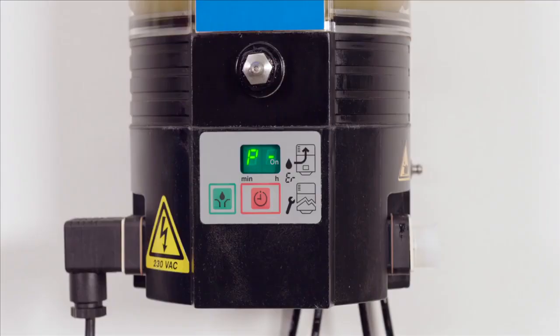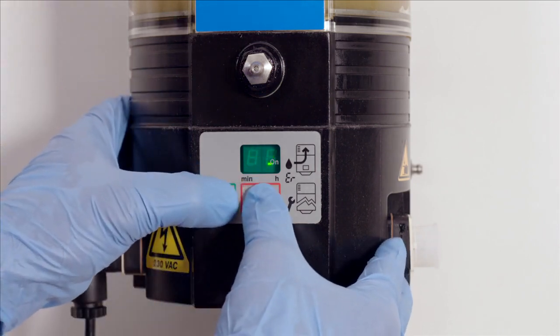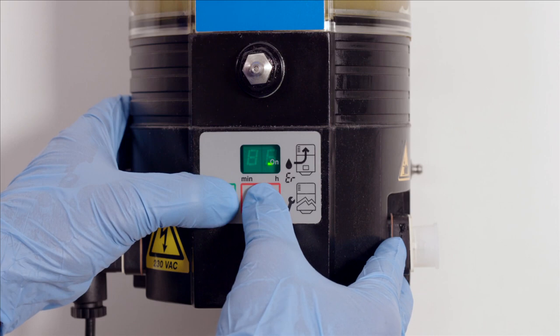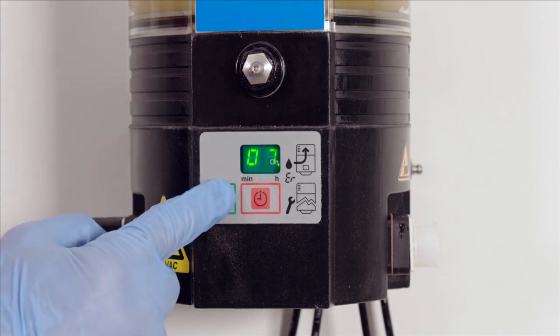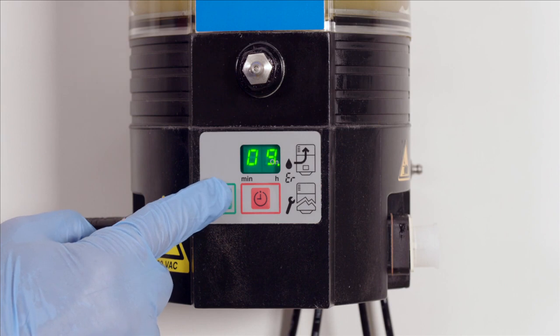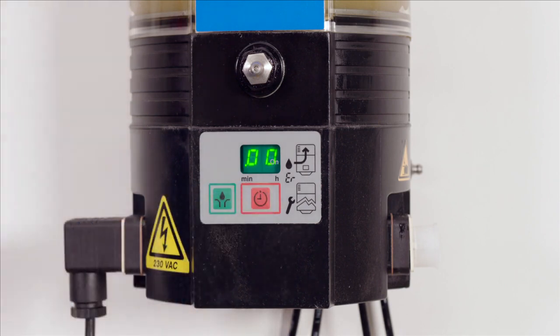To enter the programming mode, simultaneously press the green and the red keys in the keypad during at least 4 seconds. P1 should be displayed. In P1, the hour value of the pause time can be selected. Change the value by pressing the green key. Once the desired value is displayed, press the red key within 30 seconds to confirm.